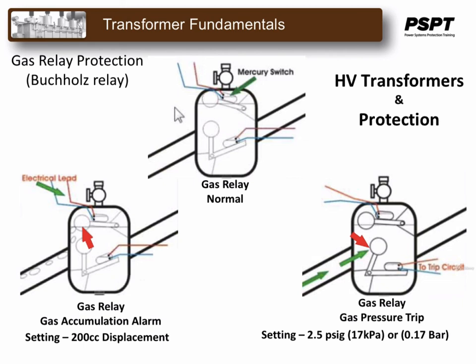If an arc forms, gas accumulation is rapid and oil flows rapidly into the conservator tank. This flow of oil operates a switch attached to a vane located in the path of the moving oil. This switch normally will operate a circuit breaker to isolate the apparatus before the fault causes additional damage. Buchholz relays have a test port to allow the accumulated gases to be withdrawn for testing.